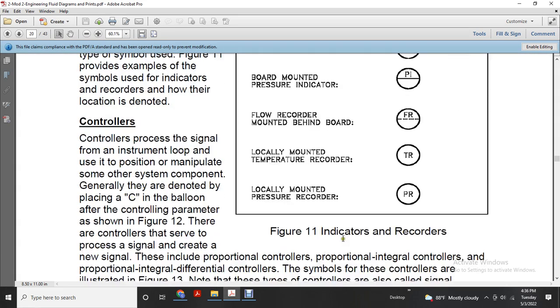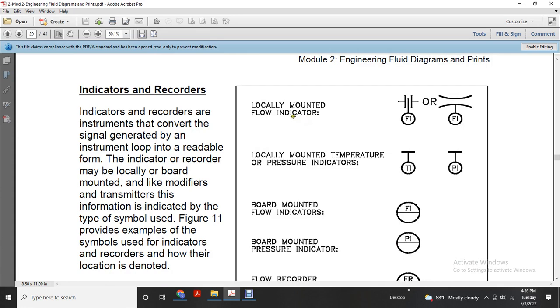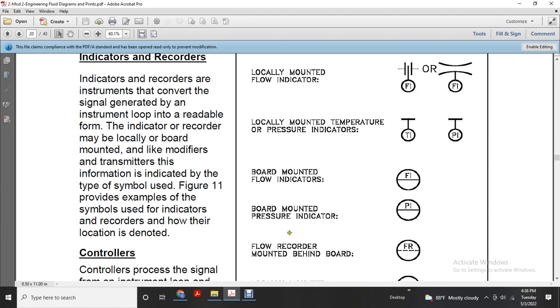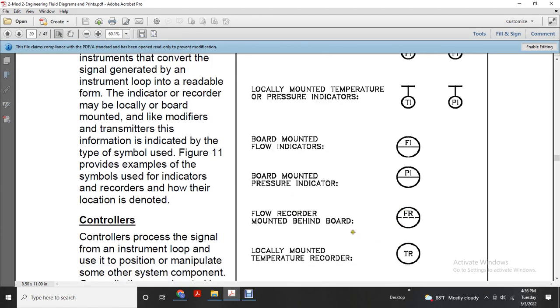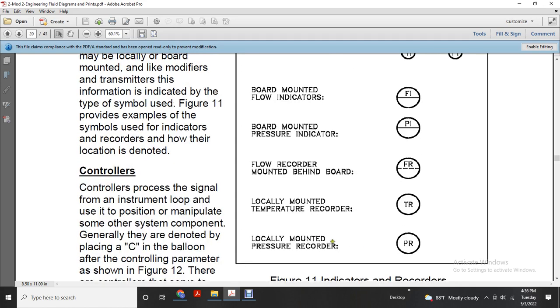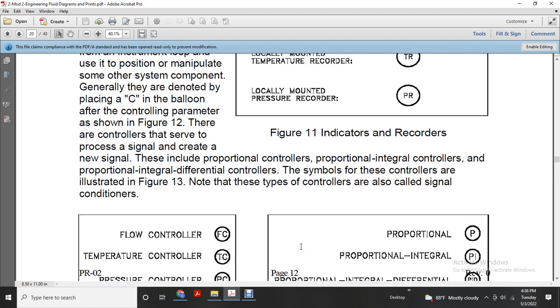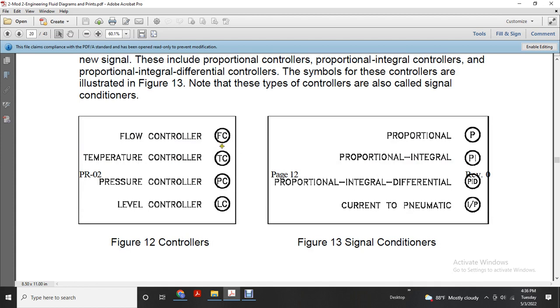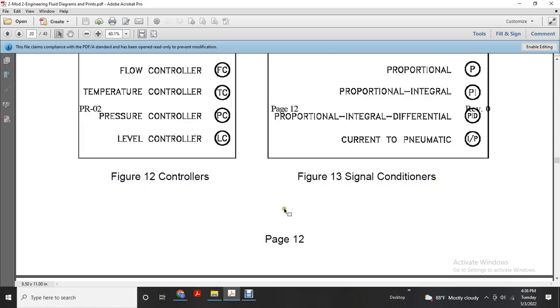Figure 11 shows an indicator recorder, with the locally mounted flow indicator with the venturi restriction, FI. It also shows the locally mounted temperature indicator TI and pressure indicator PI, the board mounted flow indicator, the board mounted pressure indicator, the flow recorder mounted behind the board, the locally mounted temperature recorder, and the locally mounted pressure recorder. Then there are the flow controller, temperature controller, pressure controller, and level controller, with proportional, proportional integral, and proportional integral differential control, and current to pneumatic.